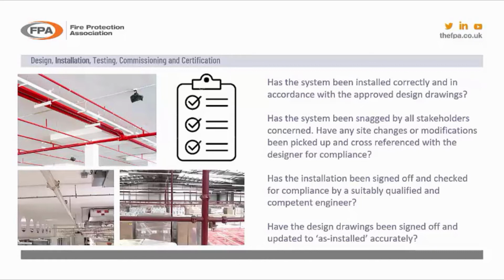Has it been correctly installed in accordance with the approved design drawings? And once it has been installed, the system should be checked and signed off by qualified, competent engineers. Any changes or modifications to the system, this is the time they should be captured, and they should be updated on drawings and sent back to the designer so that the as-fitted drawings are accurate. So the system should be snagged.